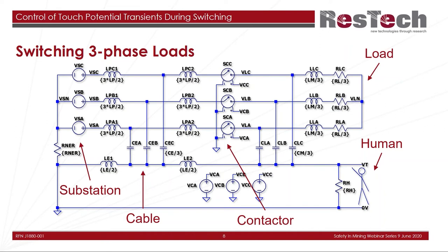And ideally, if those capacitances weren't there, it would be a lot easier, because it'll be this path that we will see the current actually flows through to generate our touch potential. So if I relate what we've had before with that, where the touch potential is actually being generated: in the previous slide, I showed an earth fault between a phase and earth. Now consider these parasitic capacitances being that path where a current might flow.